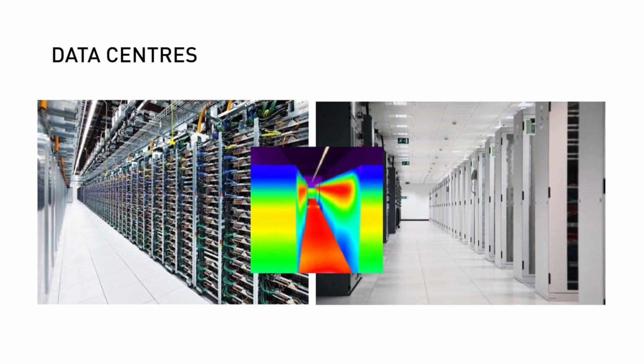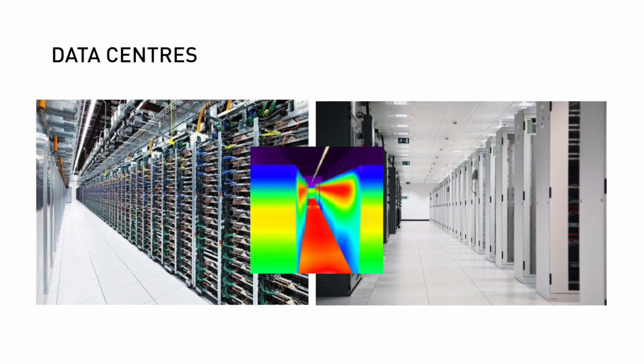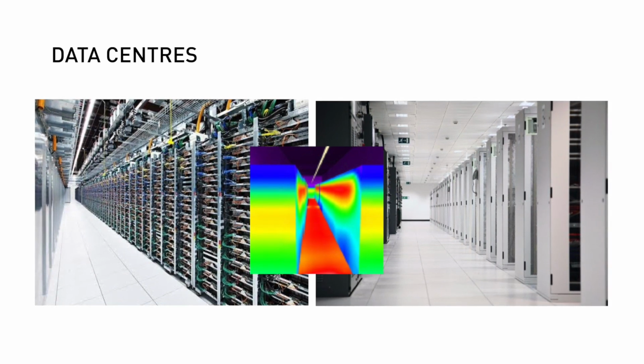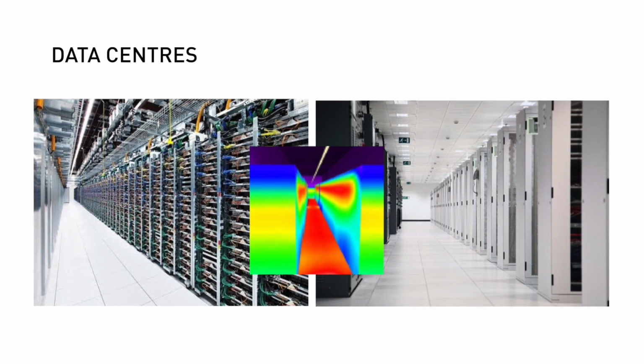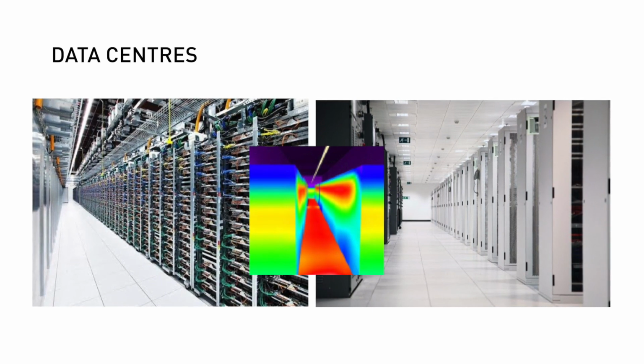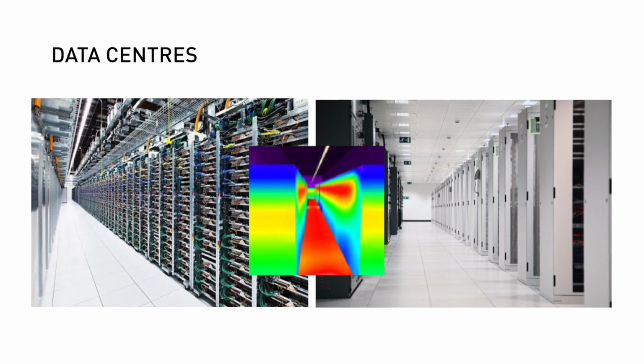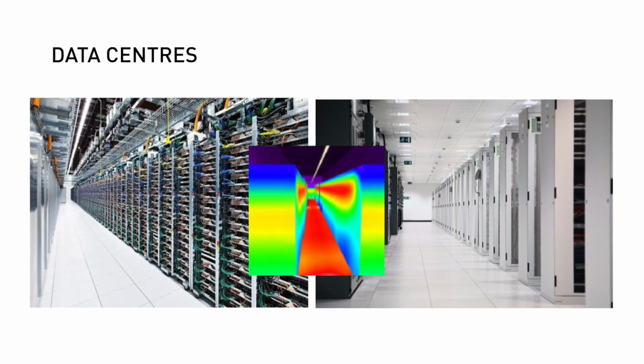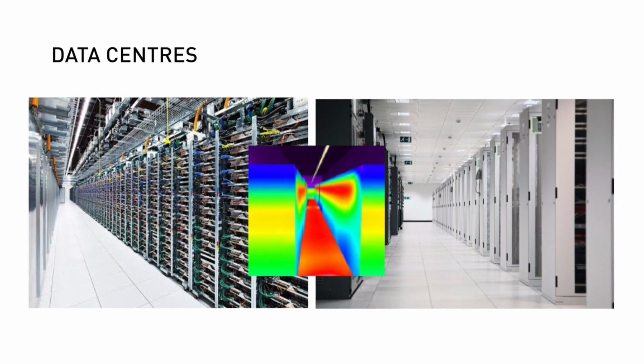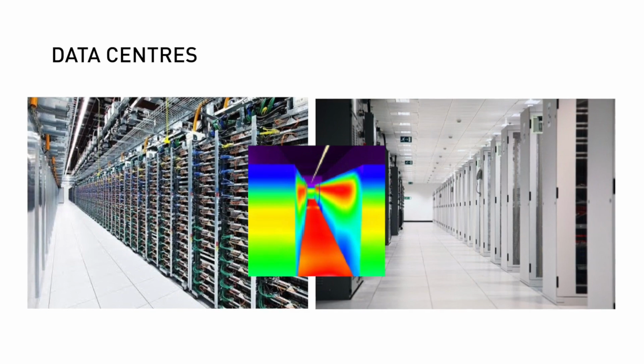And a suspended ceiling is probably not necessary in a data centre. You will find the suspended part generally on the hot aisle, because obviously that's being exhausted and then will be going down pipes. But as you can see from one of these images, they've got an open soffit ceiling. So again, as you say, it is not contained with a suspended ceiling in place. But it varies from site to site and job to job, and also from client to client. Certain clients, the owner-occupiers, have a very fixed method by which they wish to operate. Okay, so it's sort of copy and paste from data centre to data centre.